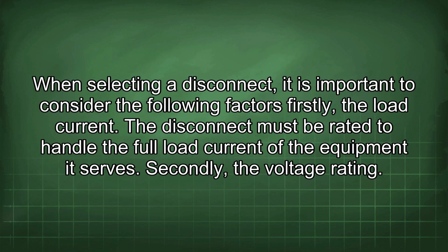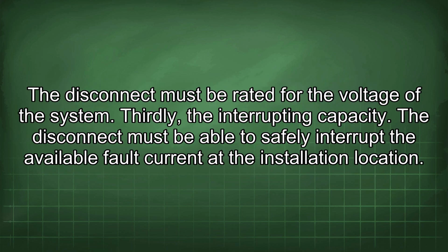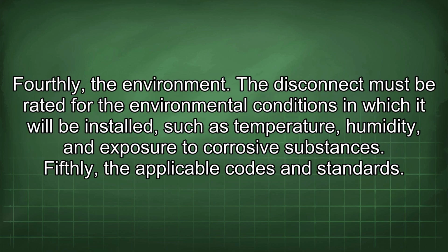When selecting a disconnect, it is important to consider the following factors. Firstly, the load current. The disconnect must be rated to handle the full load current of the equipment it serves. Secondly, the voltage rating. The disconnect must be rated for the voltage of the system. Thirdly, the interrupting capacity. The disconnect must be able to safely interrupt the available fault current at the installation location. Fourthly, the environment. The disconnect must be rated for the environmental conditions in which it will be installed, such as temperature, humidity, and exposure to corrosive substances.